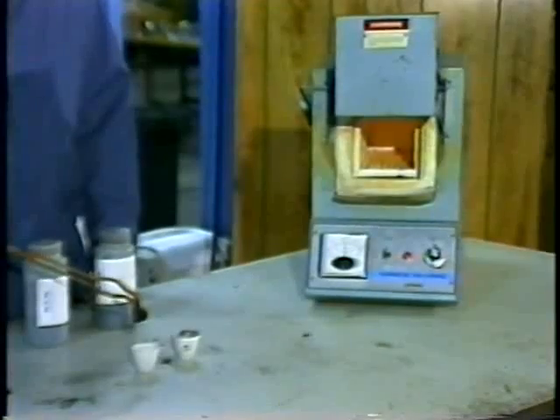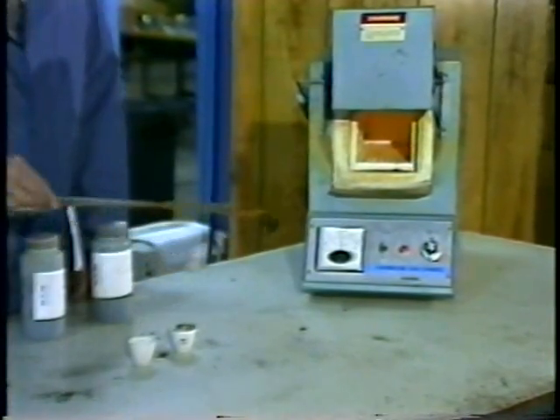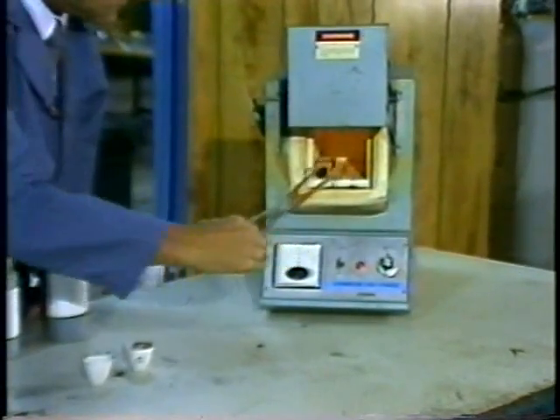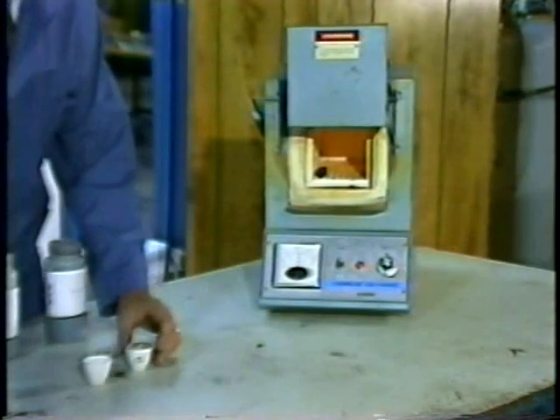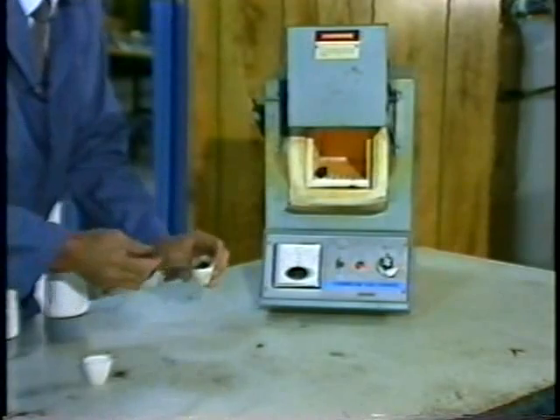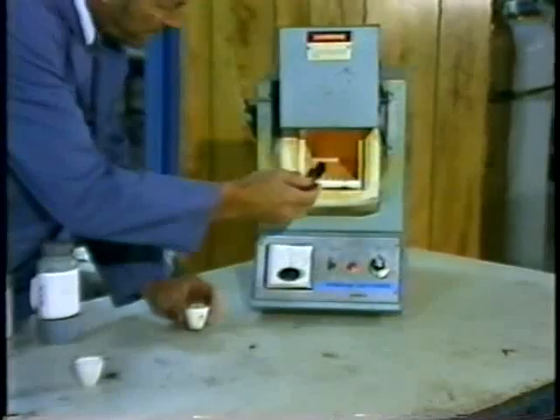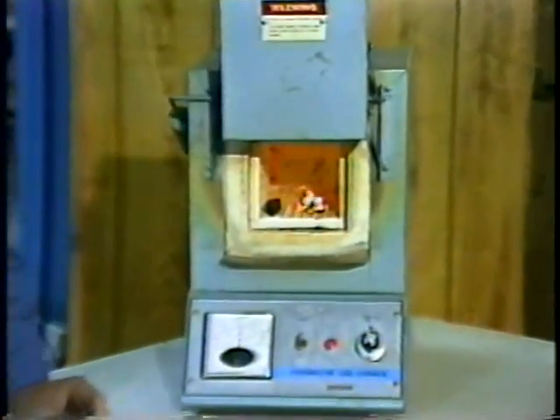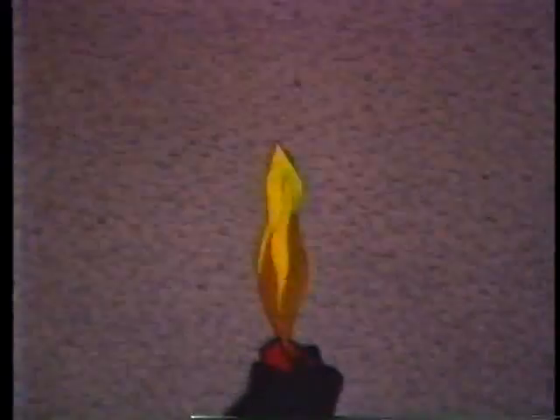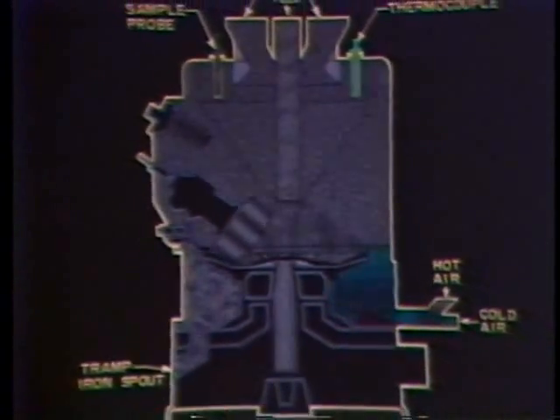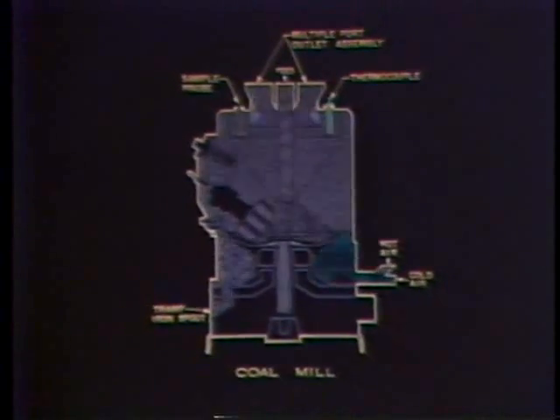Accelerated reaction speeds with the pulverized coal mean faster ignition times occur. The coarse coal will gradually ignite while the pulverized coal ignites instantaneously. The fuel-air ratio in coal systems commonly passes through the range of 1 gram per liter of air, the mixture most likely to explode with flame front speeds approaching that of dynamite. This combustible mixture of coal and air can exist in the mills and pipes of the air-conveyed coal systems, causing continual danger of fires and explosions.